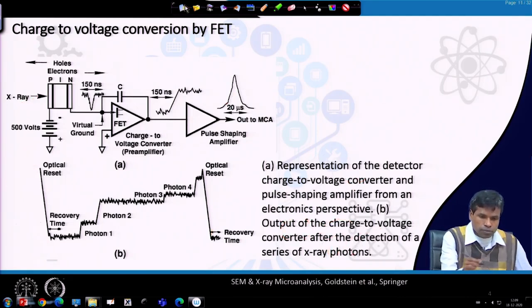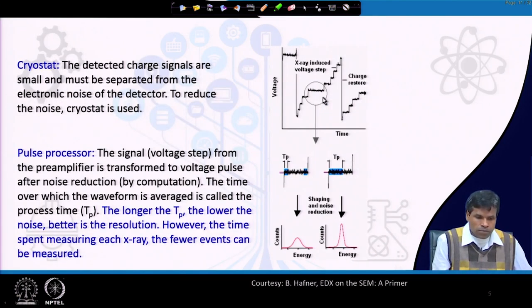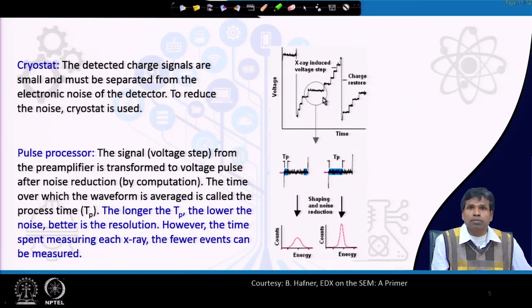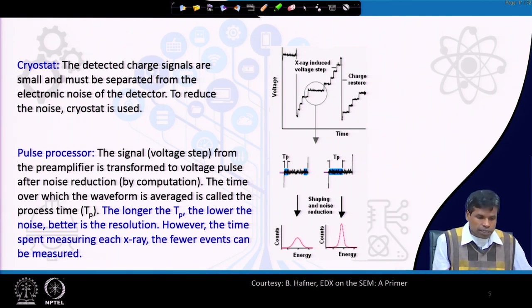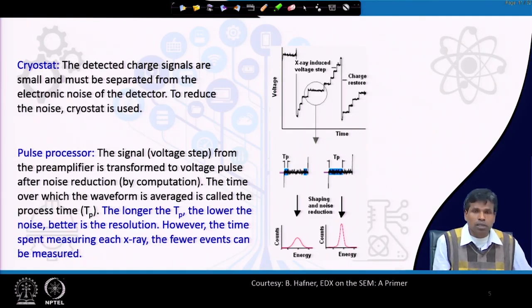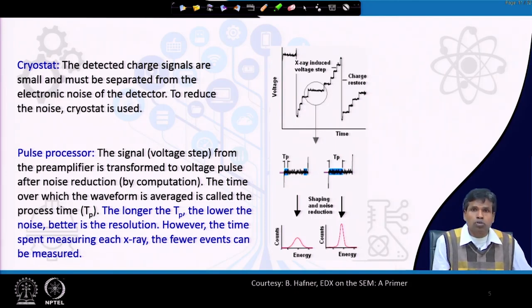We have a cryostat — as mentioned before, the detected charge signals are very small in the detector. Therefore they must be separated from the electronic noise, and the cryostat is used for that purpose. Then we have a pulse processor: the voltage steps obtained from the FET are transferred to voltage pulses after reducing the noise, and the time over which the waveform is averaged is called the process time.